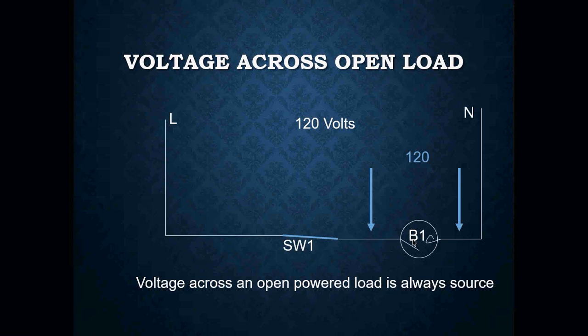Voltage across an open load, you are still going to read 120 volts. Why are we reading 120 volts? Because our load is now acting like an open switch. Our meter is picking up that difference in potential, but yet that load is not working. To confirm that this load is in fact bad, we would take a resistance reading across it, and we would see that we would read OL because the winding inside there is actually open.